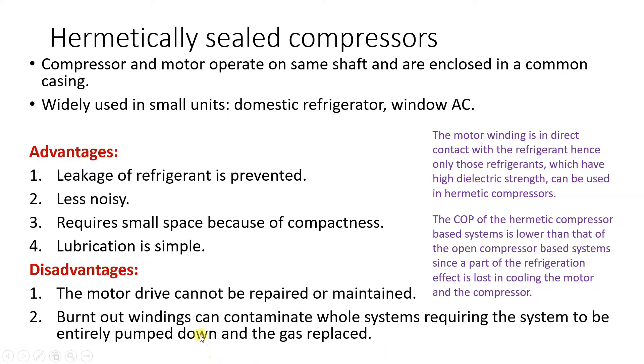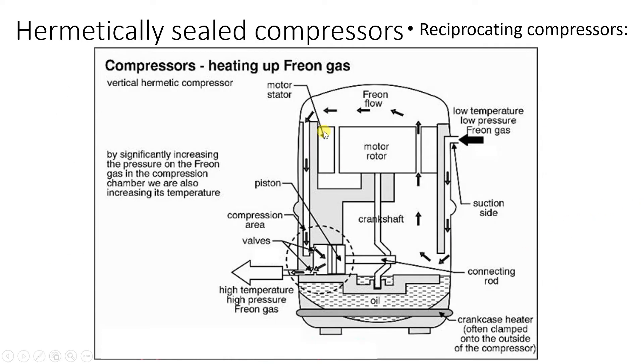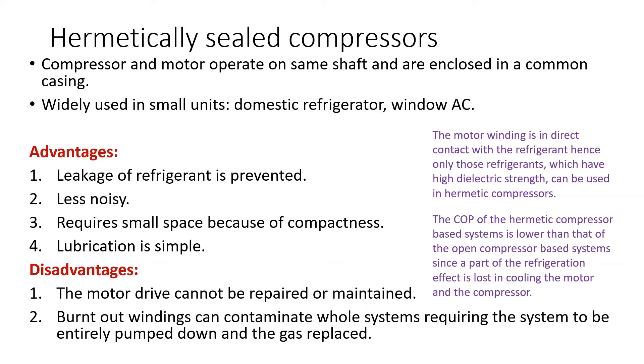Another disadvantage: burnt-out windings can contaminate the whole system. If the windings get burnt, the refrigerant is in contact with the winding and will get contaminated. Because of that the whole system will be contaminated, and the solution requires the whole system to be entirely pumped down and the gas to be replaced. The motor winding is in direct contact with the refrigerant; hence only refrigerants with high dielectric strength can be used in hermetic compressors.